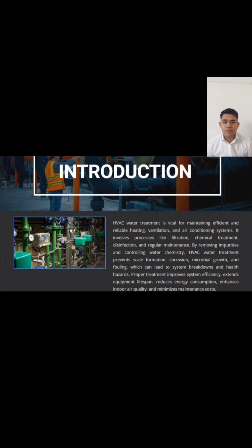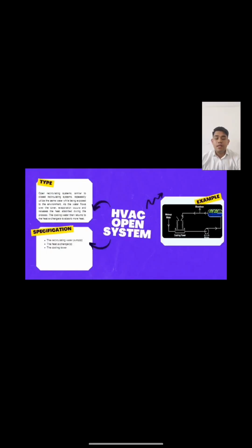By implementing effective water treatment strategies and adhering to regulations and guidelines. The first mind map is the HVAC open system. Type: open recirculating system, similar to the closed recirculating system, repeatedly utilizes the same water while being exposed to the environment. As the water flows over the tower, evaporation occurs and releases the heat absorbed during the process. The cooling tower water then returns to the heat exchanger to absorb more heat.